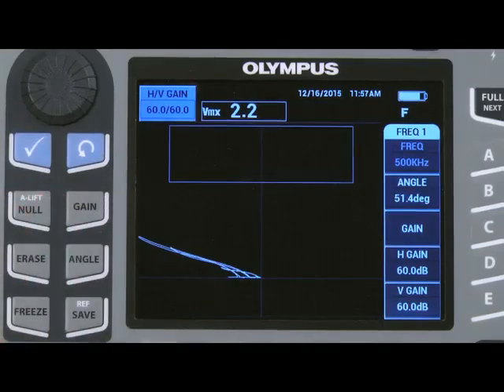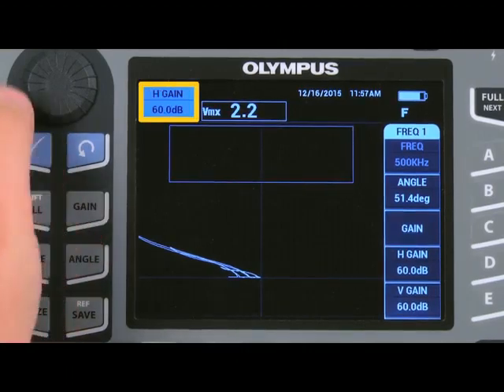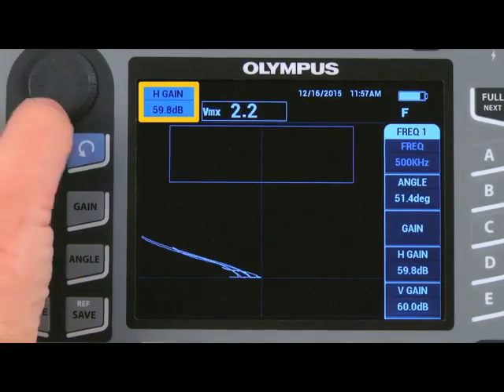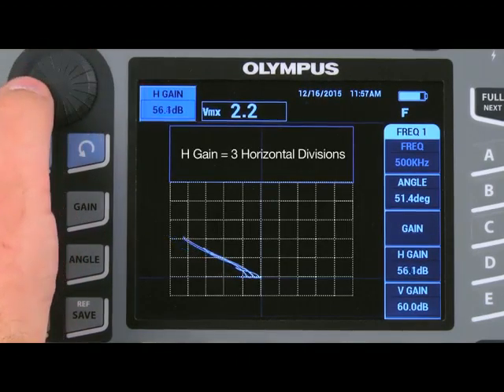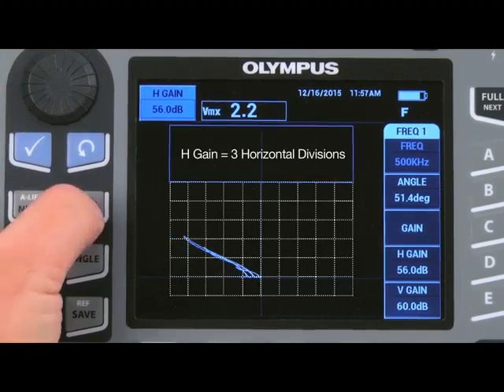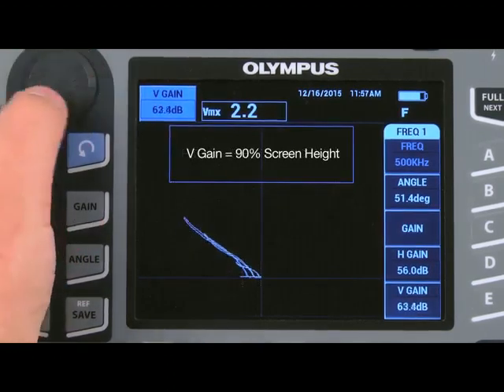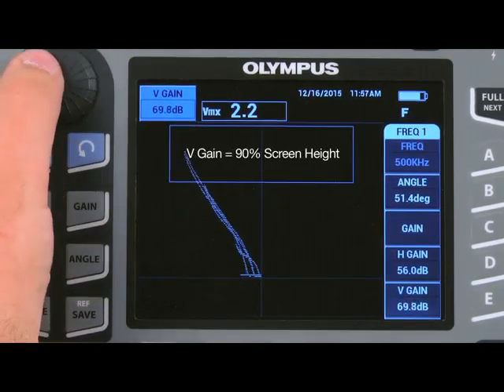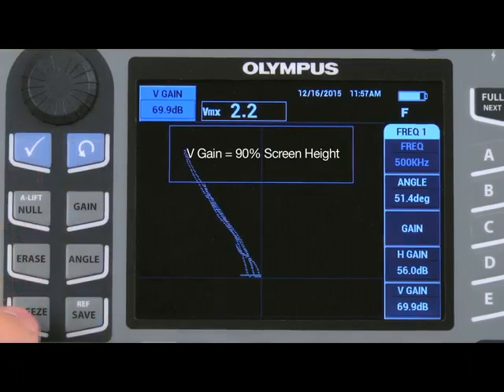Pressing the gain key once will enable the user to modify both the horizontal and vertical gains together. Press the gain key once more to modify the H gain. Reduce the gain so that the highest signal covers about 3 horizontal divisions. Press the gain key again to modify the V gain. Increase the gain so that the highest signal covers about 90% of the screen height.